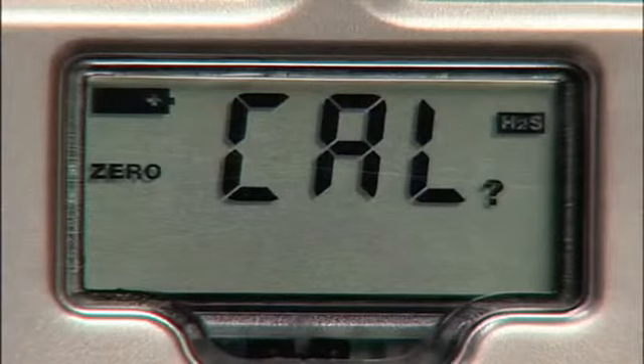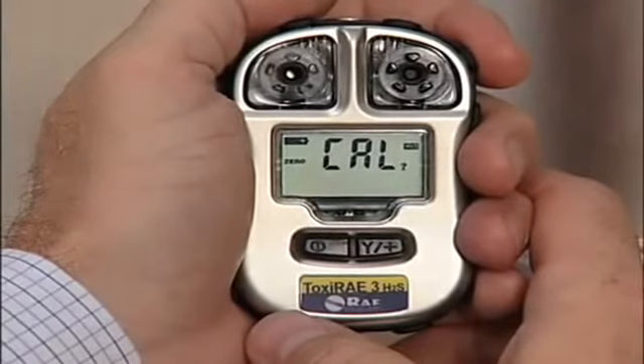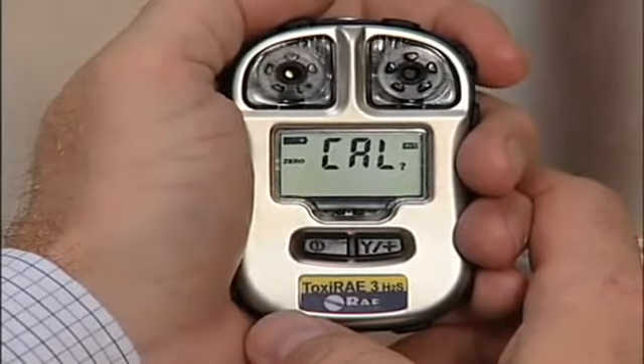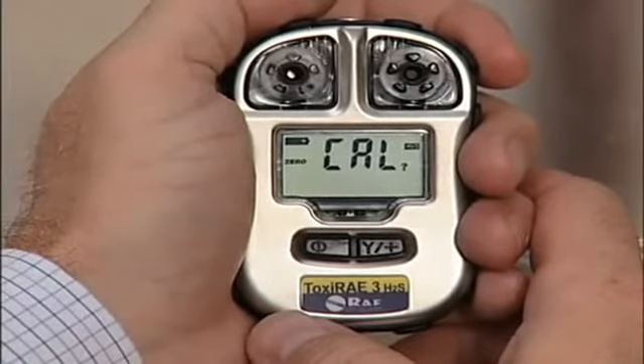Press and hold the mode button to acknowledge it and the next screen you'll see is zero cal. The ToxiRAE 3 is now ready for zero calibration, also known as fresh air calibration. Please note, if the ToxiRAE 3 is in programming mode and you do not press the key within 60 seconds, it exits programming mode and re-enters normal mode.